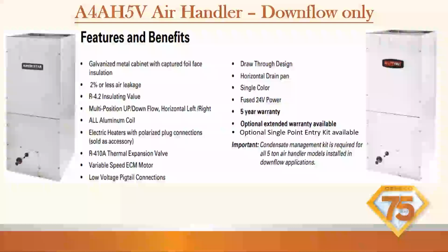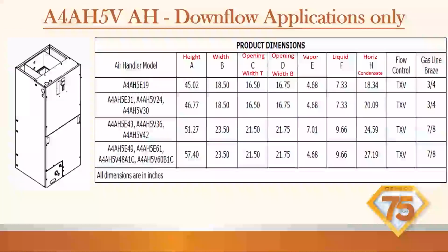Running short on time, so I won't spend too much time on these because these air handlers have been around for a little bit. It does have the TXV. This unit doesn't have a strainer though, so keep that in mind. This unit does not have an indoor strainer. Product dimensions are pretty close. We got 3/4 line set and 7/8 suction side, 7/8 3/8, 3/4 3/8.